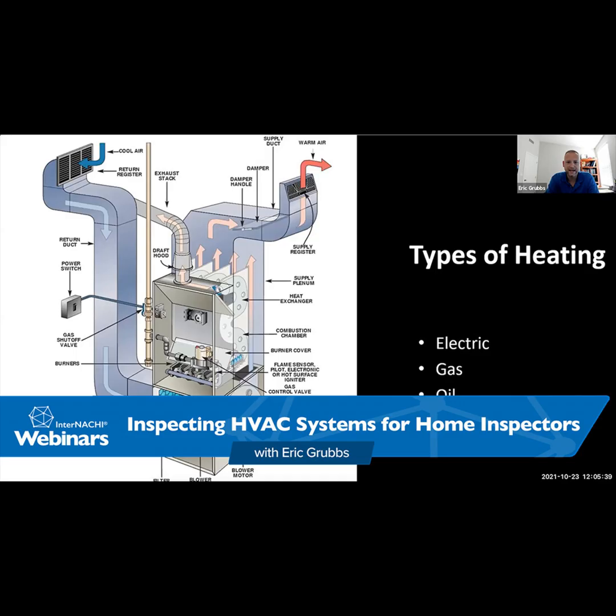A couple more slides and then we'll go on a quick short break. Single pipe systems, again, this illustrates that negative pressure in the home with a single pipe vent only exhausting out of that home, also known as a non-direct vent. They're less efficient than a two-pipe system. They freeze up less and they also cost less to install, but they're harder on the heat exchanger and the combustion air from wherever the furnace is located. Again, this depicts that air issue for combustion air, getting proper combustion to that furnace.